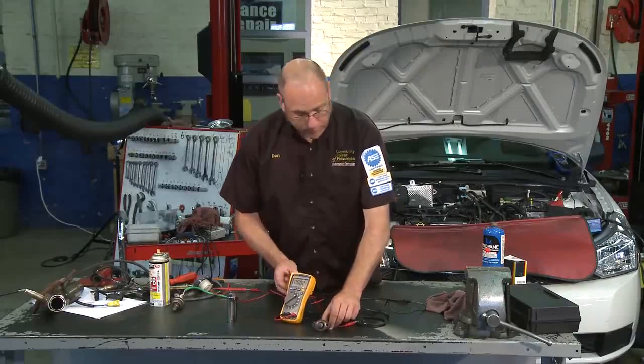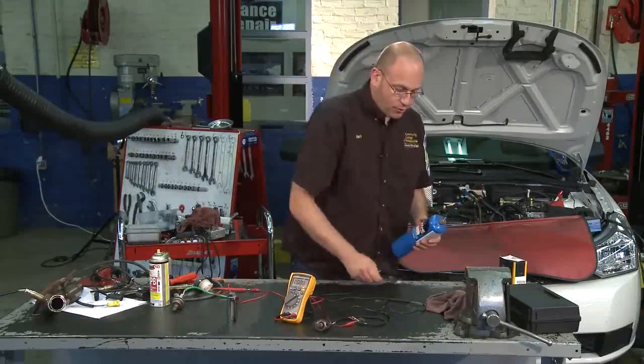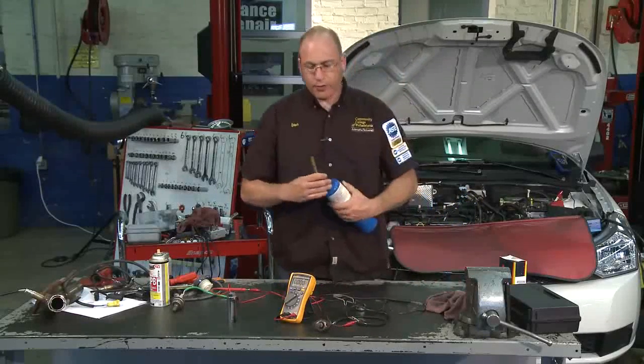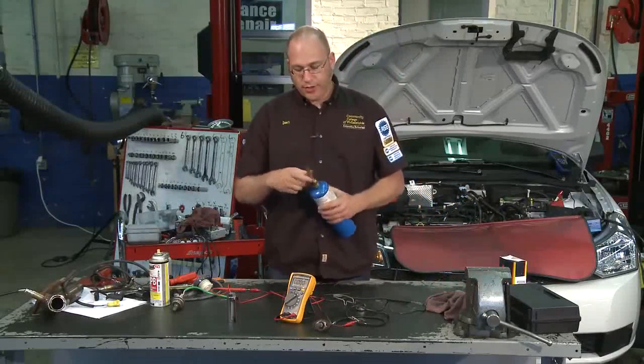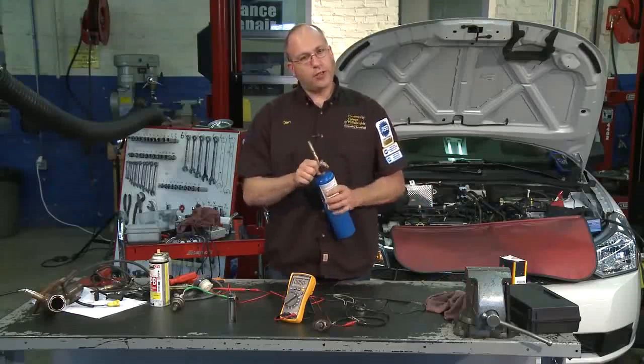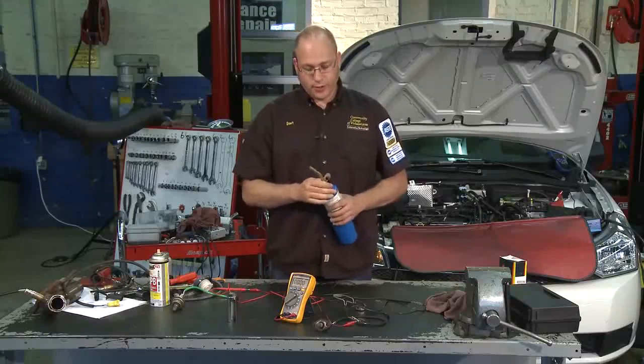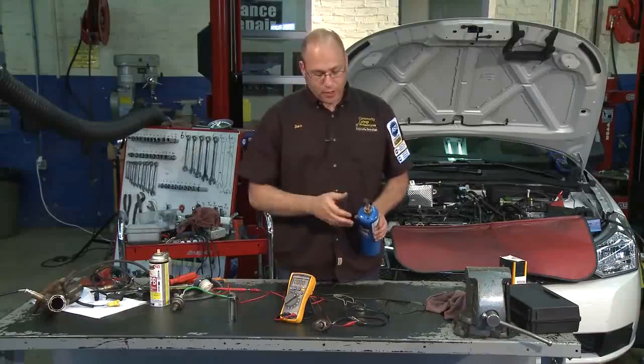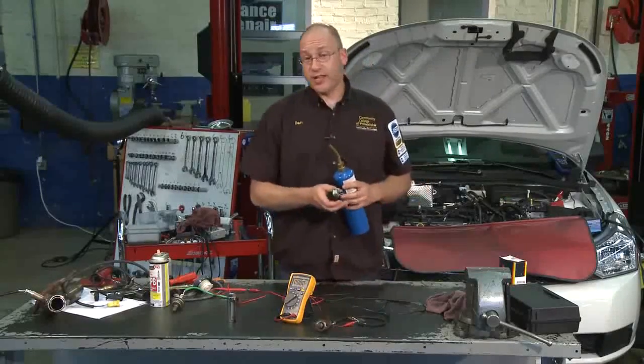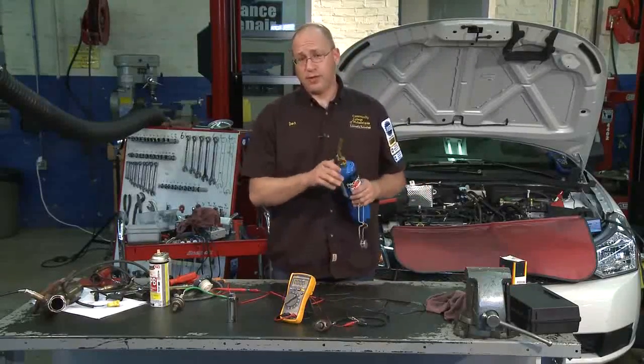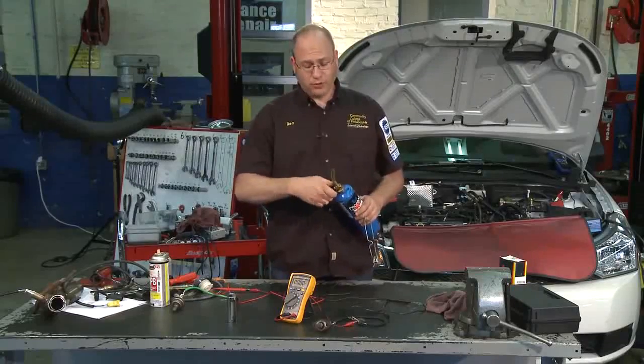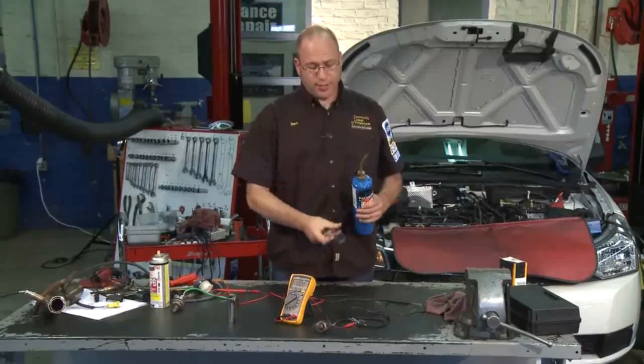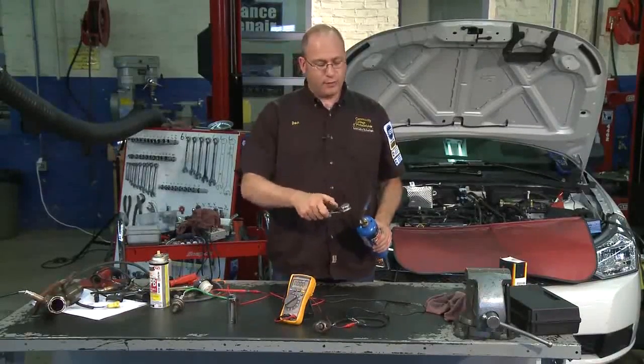But what I'm going to do is take a propane torch and heat the sensor. You're going to see that the voltage is going to start to rise on the sensor as it heats up. Now if you remember, the sensor has to get to 600 degrees, and that's a pretty big chunk of metal, and this is just a propane torch. That means it's going to take a couple seconds, if not at least a minute, for this to start to heat up.